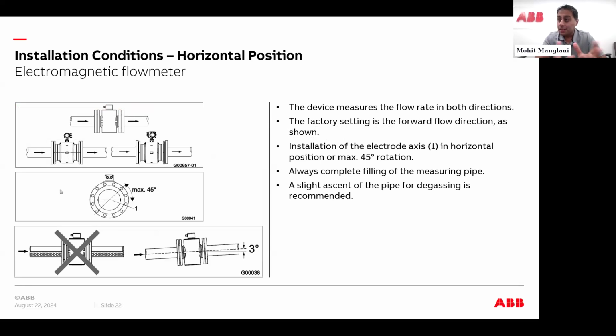Horizontal position. Obviously, depending on your installation, whether you're inside the fence or outside the fence of your facility, if you're doing a horizontal installation, try to give it a 3 degree incline and not to exceed 3 degrees up on the piping. The reason we say that is because if there is air or air bubbles in the line, or entrained air inside the liquid, depending on your application, you want it to get free. So having that little bit of an incline, it's not recommended to go fully horizontal. It's always recommended to have a slight incline. This is kind of where I see the biggest challenges coming of installations and specifications. Degassing is very important. Again, you've got to avoid air or any kind of gas inside the line.